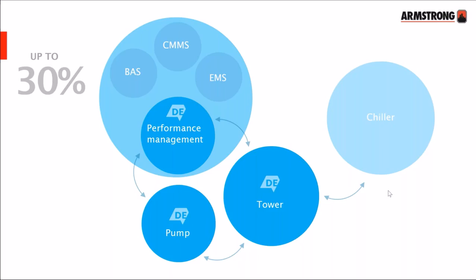We could look at converting the towers to variable flow, or we could even header the towers. These integration and optimization steps further provide flow insights into the plant and building requirements that can deliver up to 30% energy savings. Only after these steps are complete do we finally move on to the larger plants such as boilers and chillers.